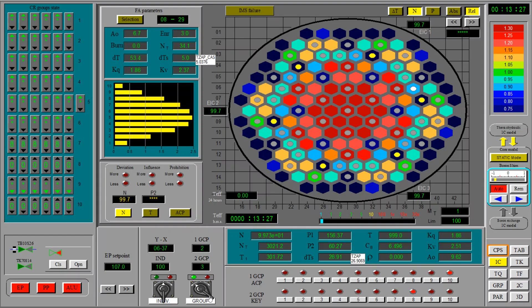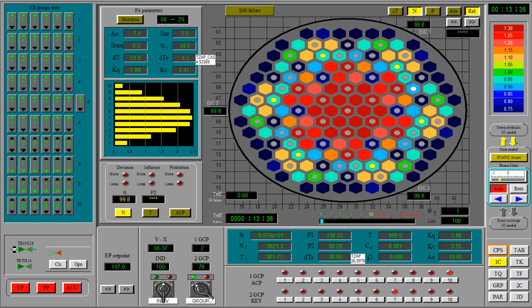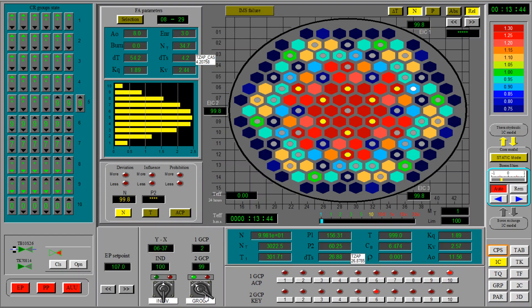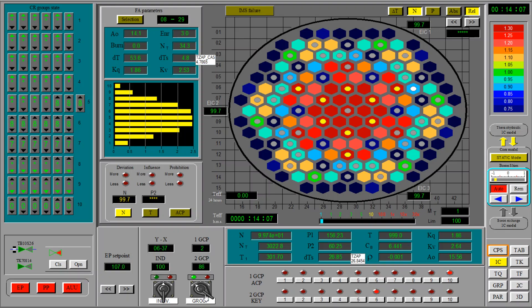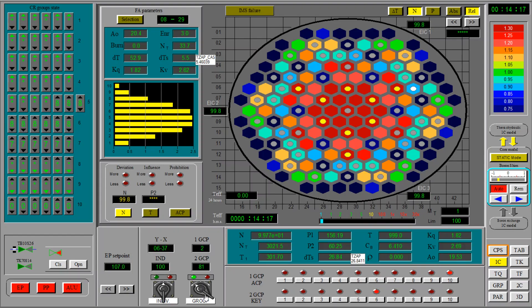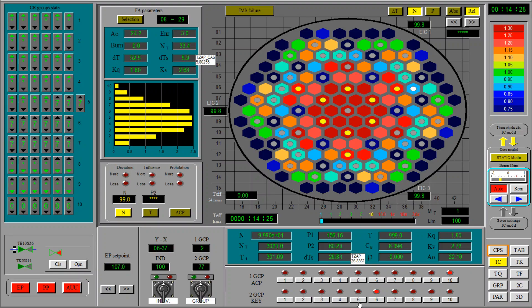Time to look at the 3D plot - we're at 9 degrees of boiling. We can see this here, the reserve before boiling is 8.7. It's the central rod, the most dangerous now. We're at 7 degrees of boiling. The problem I'm thinking about is that I wanted to withdraw group 6 to increase reactivity in the central inner part, but group 6 is already totally withdrawn. Once we reach boiling point and I stop the boron shim, I'm not sure what to do to prove my point. We're at 5 degrees of boiling. I think I will insert group 6 a bit so I'll have some available reactivity.